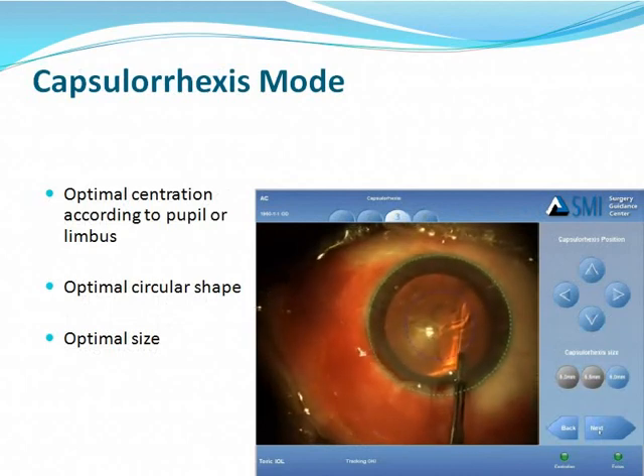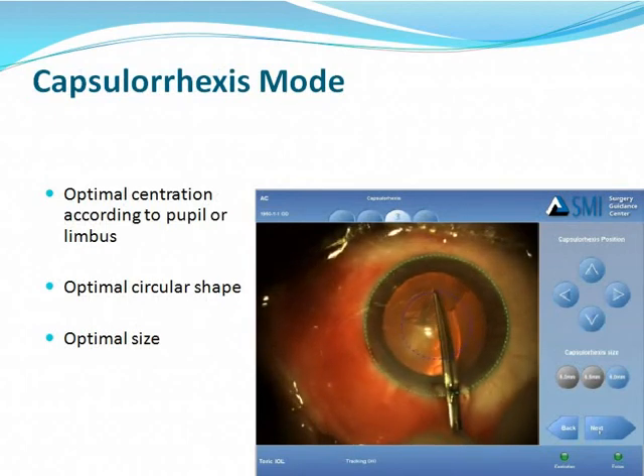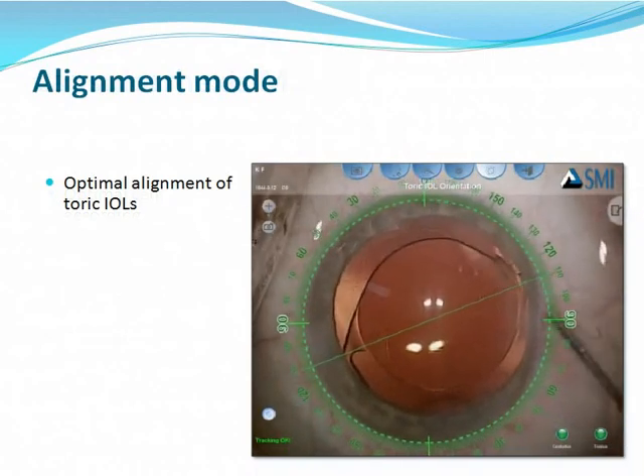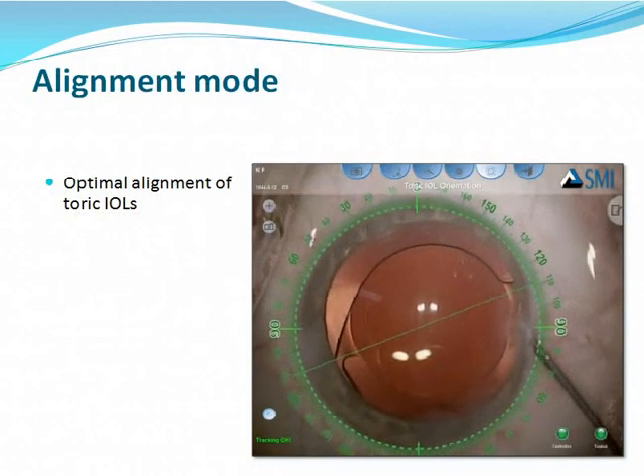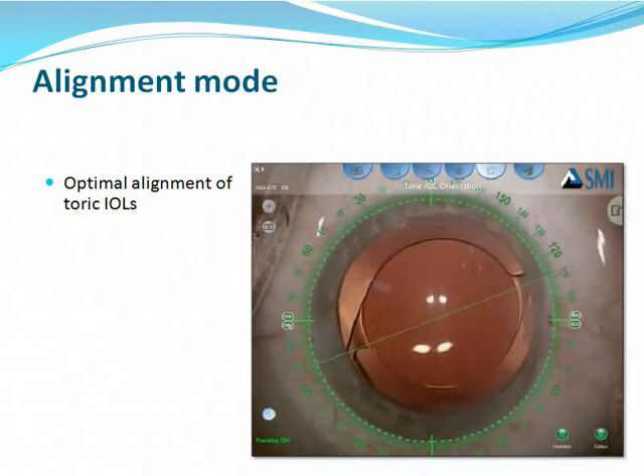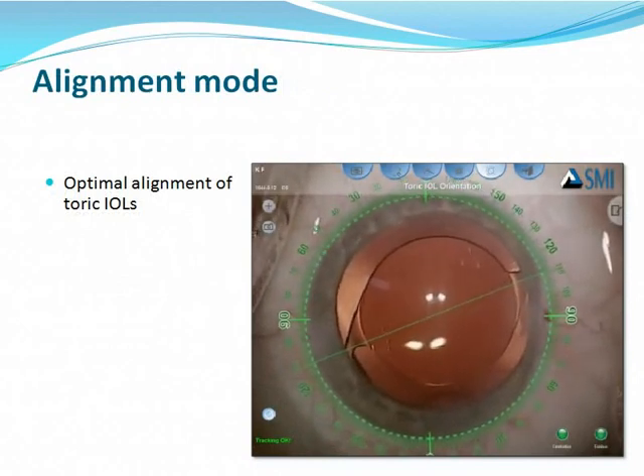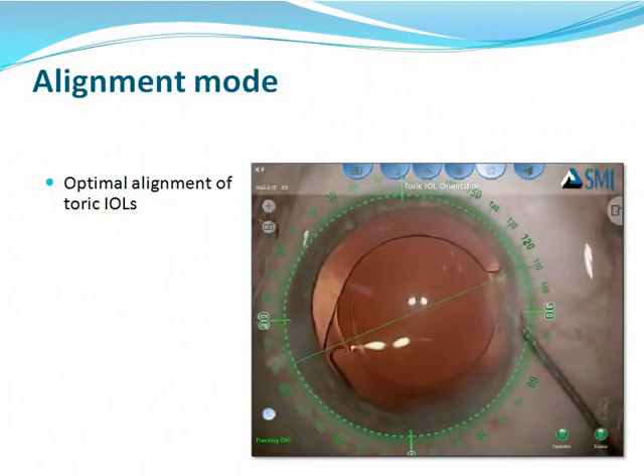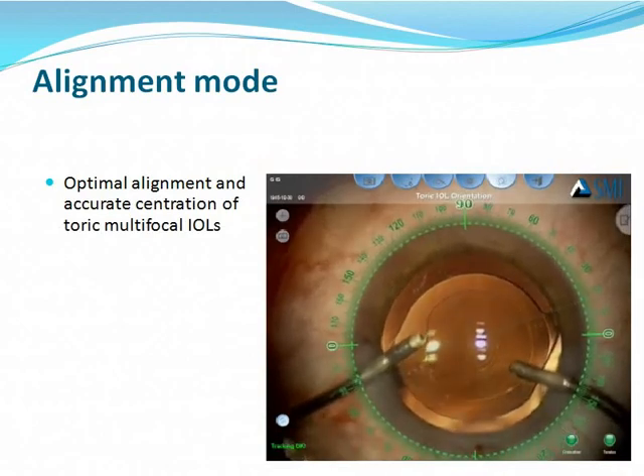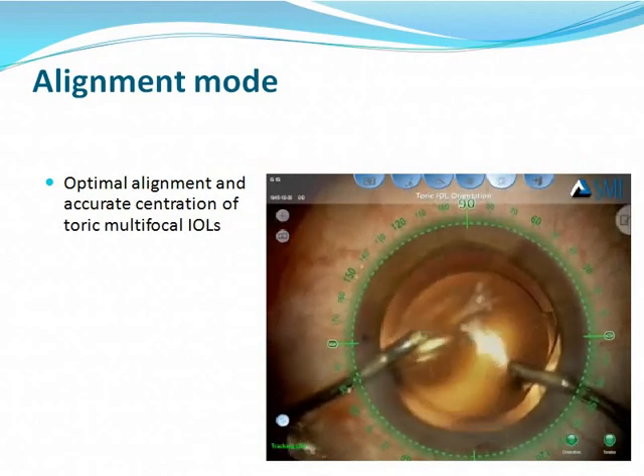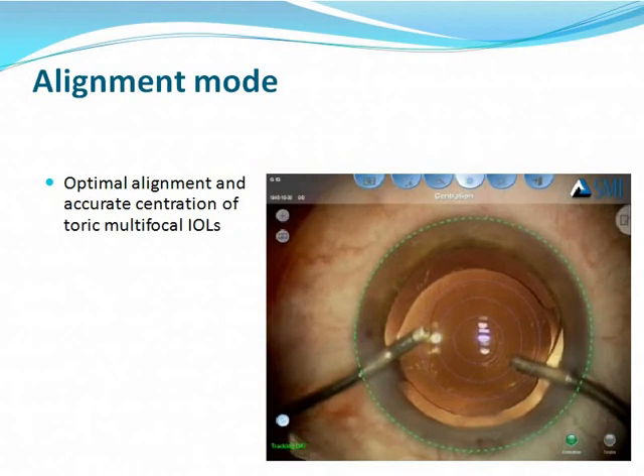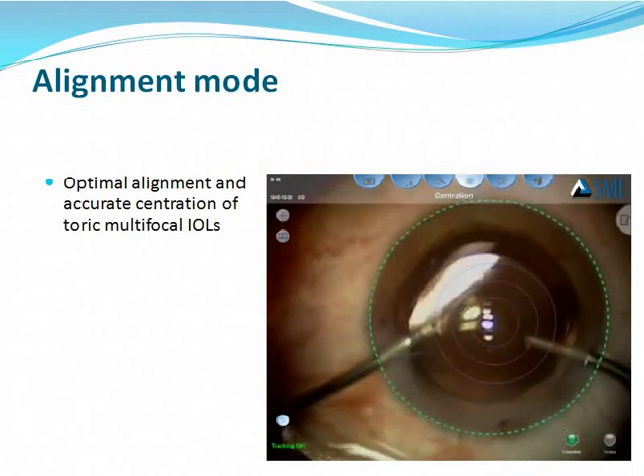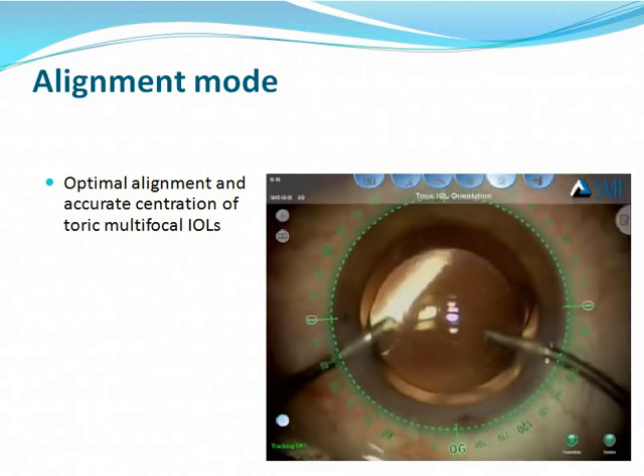This overlay is projected in your microscope view and is compatible with all microscopes. For toric IOL alignment, you can see the alignment axis, and there are two small markers next to it because alignment marks can sometimes be parallel to but not exactly on the axis — this is an excellent way of creating optimal alignment. For multifocal lenses, you can center the lens on rings projected into your screen. You can centrate these rings on the limbus or, if you wish, on the dilated pupil — it is always a choice you can make according to your preference.